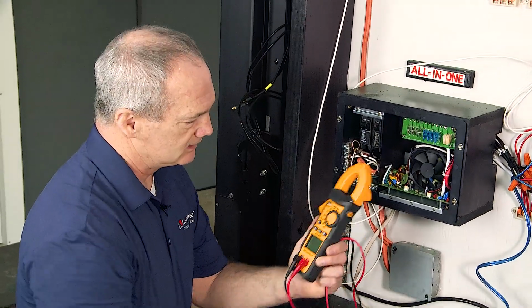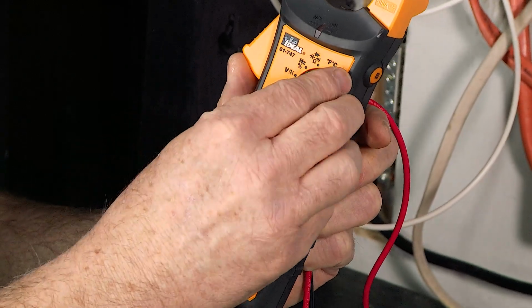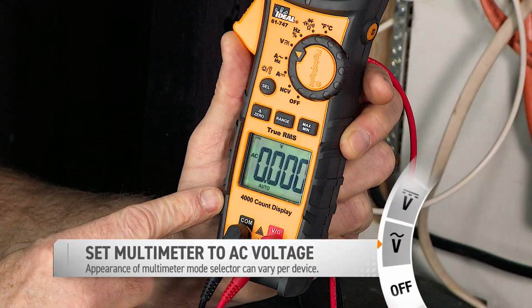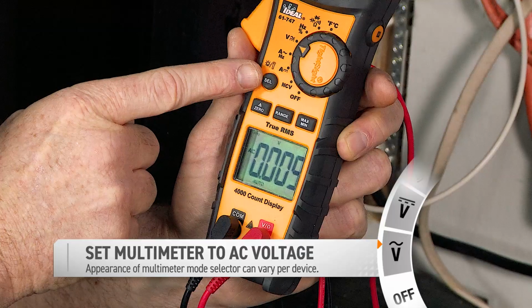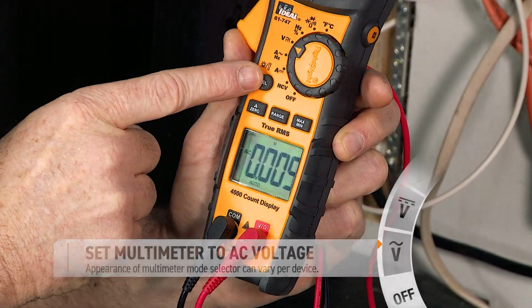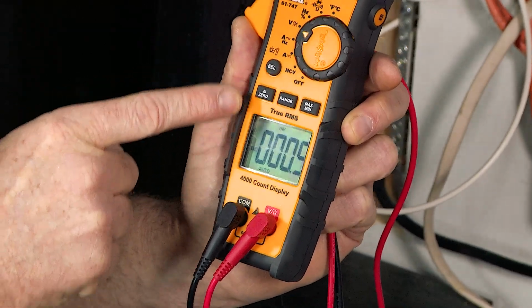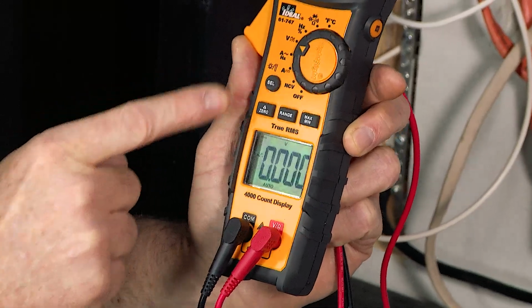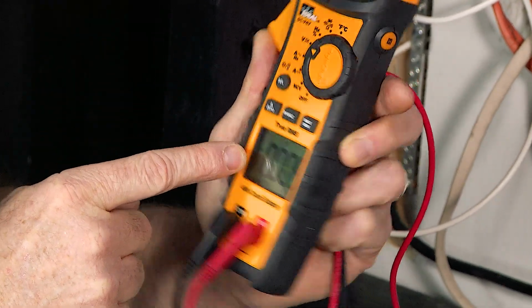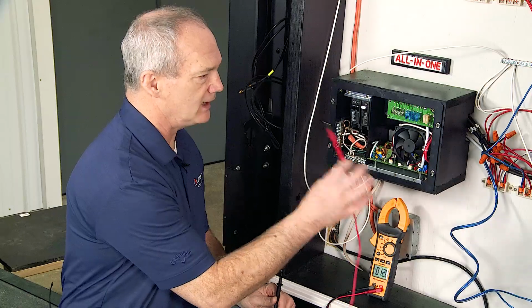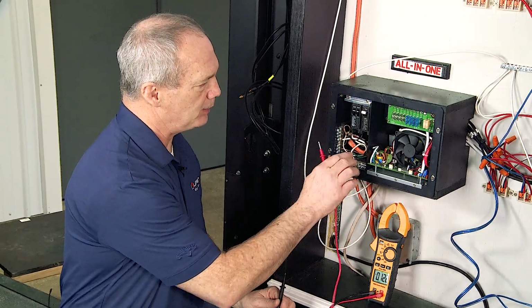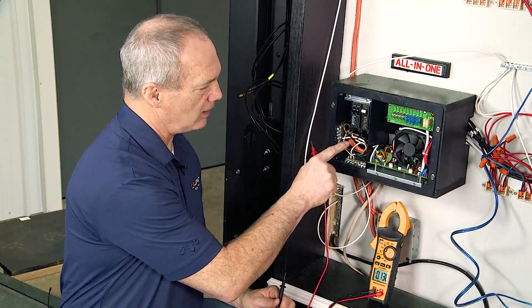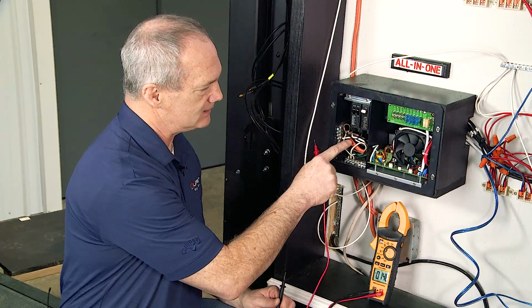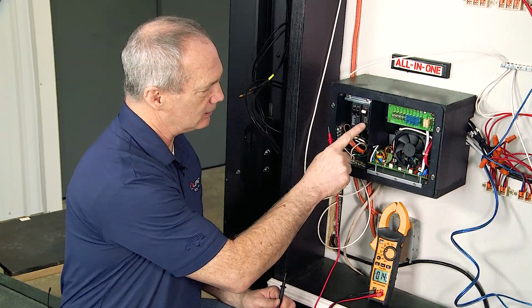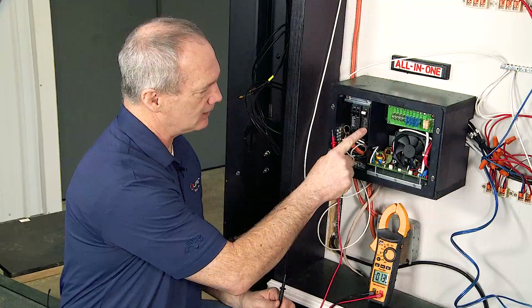You're going to set your multimeter on voltage and then change the select button. All multimeters are different, but for this one, press that button and make sure it says AC. Your first step is to take the positive probe and put it on the power lead from your 120 volts AC coming in on this orange wire, which goes to this 30 amp circuit breaker.